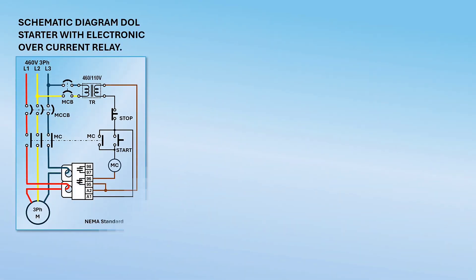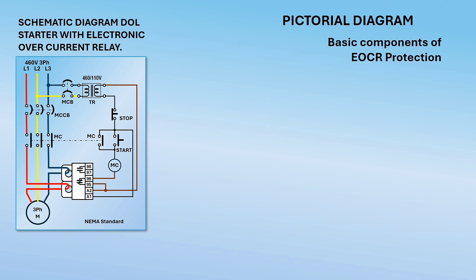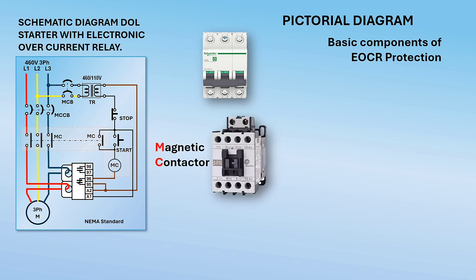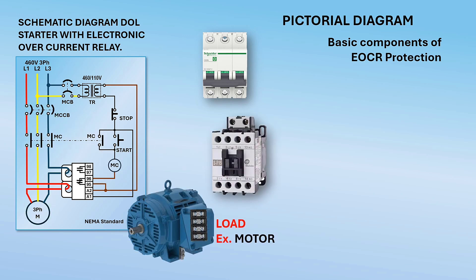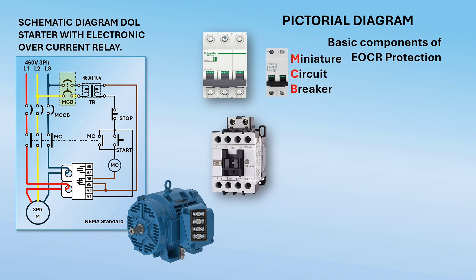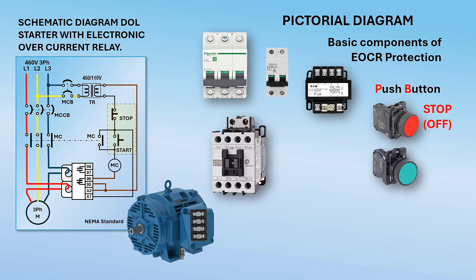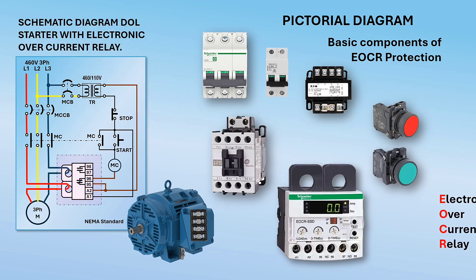Here is the schematic diagram using NEMA standard. Let us assemble a simple across-the-line DOL starter with an EOCR and other components that will complete the motor starter: molded case circuit breaker, magnetic contactor, the load — a three-phase motor, miniature circuit breaker, isolation or step-down transformer, start and stop push buttons, and the EOCR or electronic overcurrent relay.